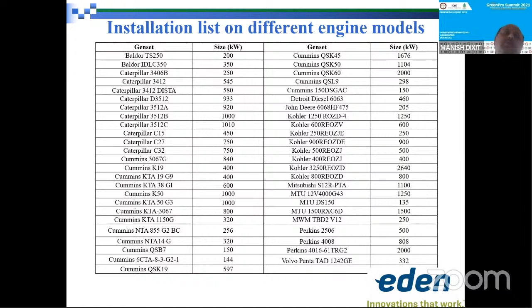Believe me, it's a fantastic product, people have used it far and wide. This is an installation in Assam, where we've received 3 repeat orders. These biofuel systems have been installed in 3 of our tea gardens within Assam, each running satisfactorily for more than 10,000 hours to date, saving diesel up to 60%. In Assam during winter they don't pluck leaves, so load requirements are very low, making this an averaged-out number. But during peak time, I got the best displacement of 73% in Assam, meaning 73% of diesel was saved, with 60% being the average over a couple of years.